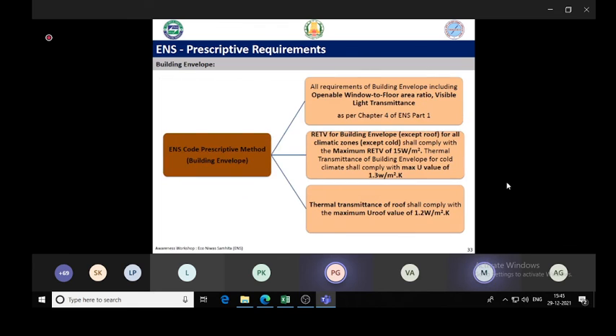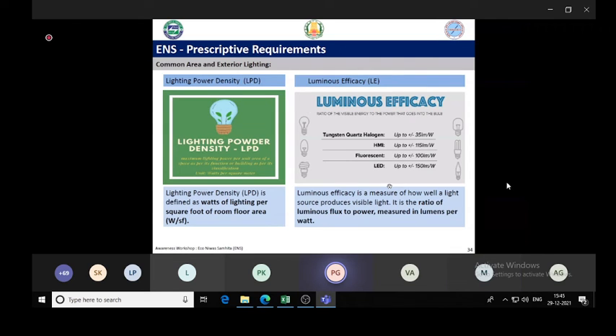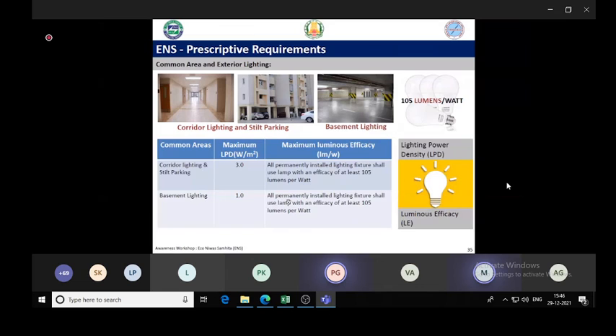And coming to the prescriptive approach, in lighting systems, in the prescriptive requirement, they specify the LPD, lighting power density, similar to ECBC. There are 2 options given. Either we can comply with LPD or we can comply with the luminous efficacy, which is your lumens per watt. So either of these needs to be complied with, and there are tables given.